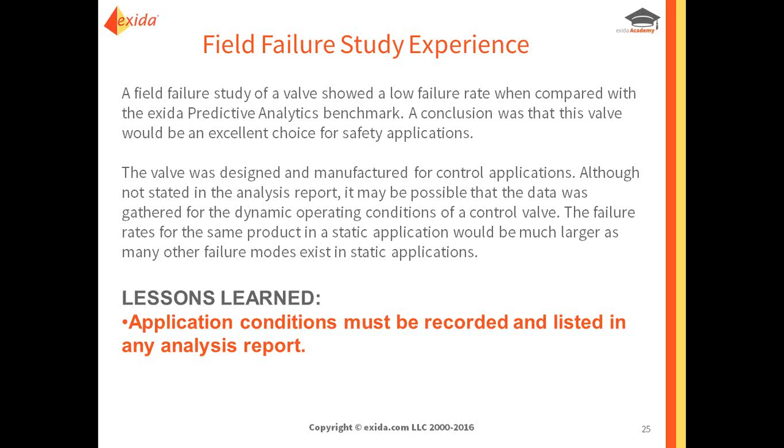Although not stated in the analysis report, it may be possible that the data was gathered for a dynamic operating condition of a control valve. The failure rates for the same product in a static application would be much larger, and many other failure modes exist in static applications.